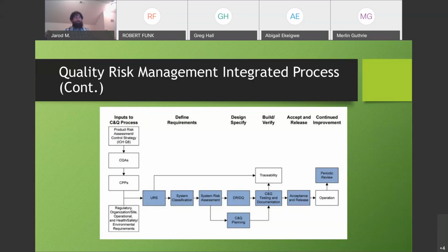So then into the system classification, and we'll discuss that classification a little more on the next slide. But what is the risk? Really assessing the risk to product, to patient, with that individual system. And these can be broken down into the high-level system and then also the individual subsystems within a piece of equipment. Moving on into the system risk assessment, and we'll get into a little more detail on that in a minute. And then to your design requirements, design qualification, into your commissioning and qualification, testing and documentation. So it's a lot of planning, assessment, development, and then getting into actual verification task activities and all traceability.